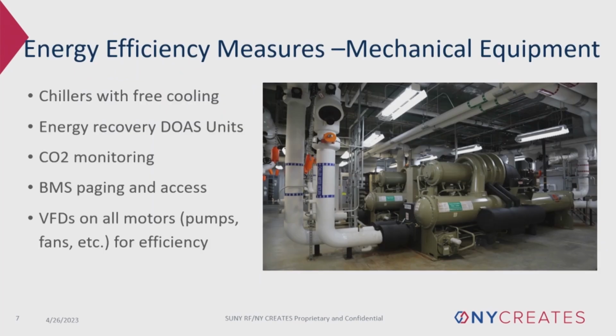In terms of the mechanical equipment that's been installed in this building, the chillers are capable of free cooling, which allows us to cool the building in the winter utilizing ambient temperatures instead of running mechanical cooling. We have energy recovery on the dedicated outdoor air units, which allows us to harvest energy before we send it out of the building to precondition the air. We have CO2 monitoring, which allows us to introduce just enough ventilation air so that occupants are comfortable and we're meeting code without needing to overcool or overheat any outside air we're bringing in. We also have BMS paging 24/7, which allows the technicians to respond when something's not operating as it should. And there are high efficiency VFDs on all pumps, fans, pretty much any motor.